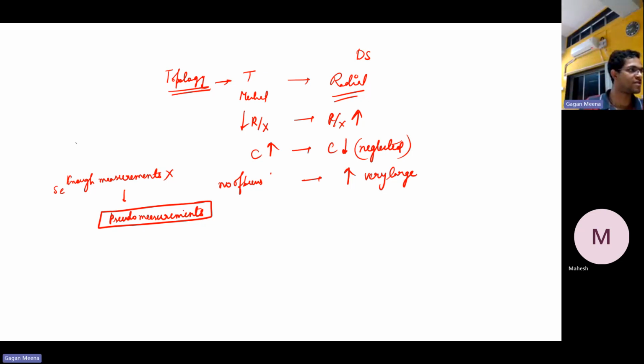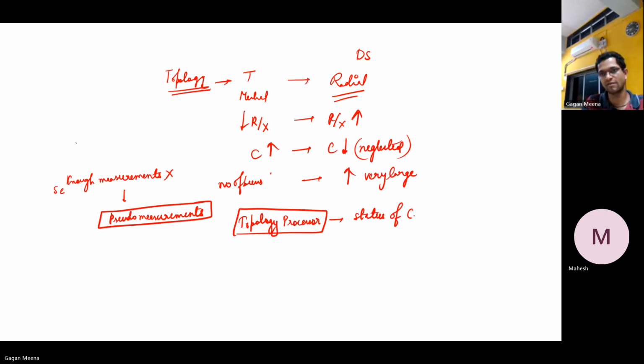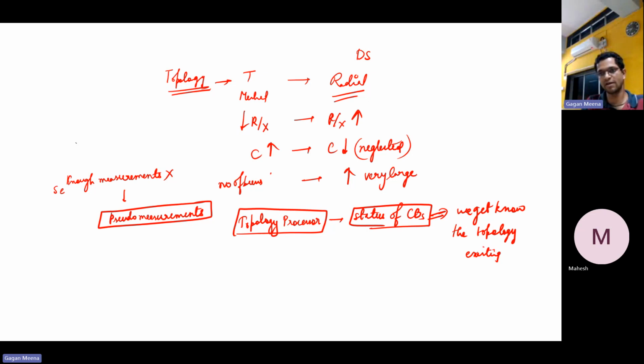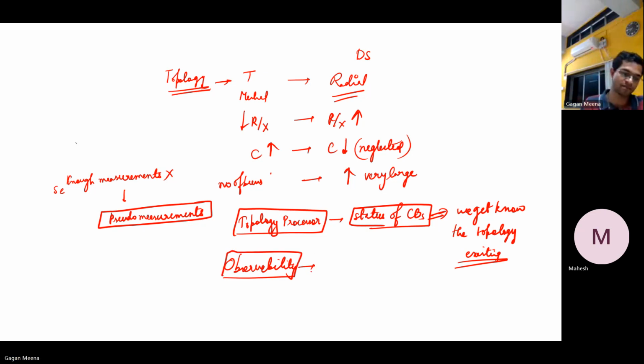Now we have different functions of the state estimator. The first block of any state estimator is the topology processor. Based upon the status of circuit breakers, we first of all get to know the topology of the network; the existing topology needs to be obtained first. And then, once we know the network at a particular timestamp, we do the observability analysis. Are the measurements enough?